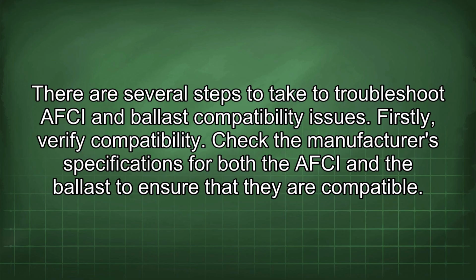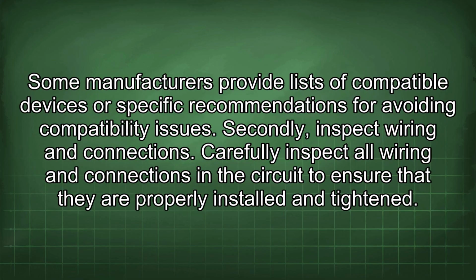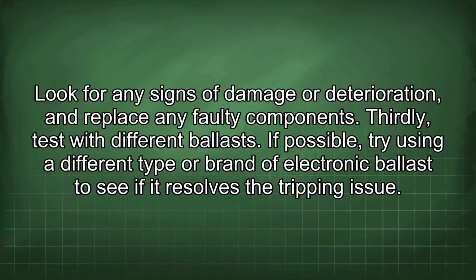There are several steps to take to troubleshoot AFCI and ballast compatibility issues. Firstly, verify compatibility. Check the manufacturer's specifications for both the AFCI and the ballast to ensure that they are compatible. Some manufacturers provide lists of compatible devices or specific recommendations for avoiding compatibility issues. Secondly, inspect wiring and connections. Carefully inspect all wiring and connections in the circuit to ensure that they are properly installed and tightened. Look for any signs of damage or deterioration and replace any faulty components. Thirdly, test with different ballasts.